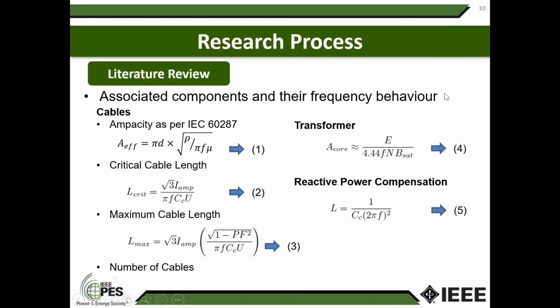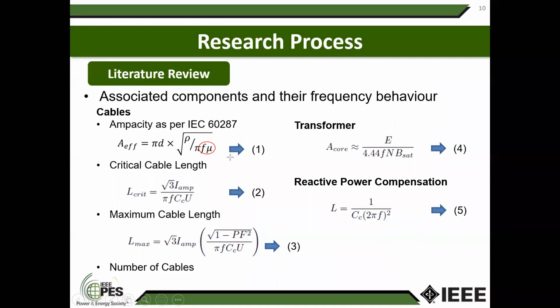Then, of course, from the literature review, you can work out the frequency dependency of different components used in these wind farms and altogether in the wind park. If you look at cables, IEC 60287 defines the ampacity, or the current carrying capacity of a cable, and you can see clearly it has a frequency component here. So frequency component there, so it is frequency dependent. Then the critical length that your cable can have, depending on the reactive power generated by the cable, again there is a frequency term. And the maximum cable length, again there is a frequency term.